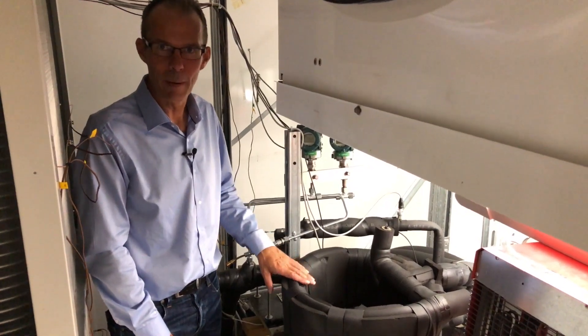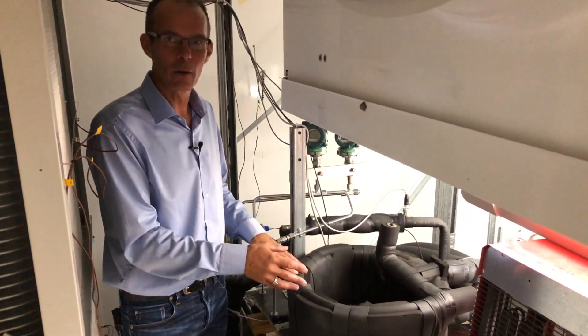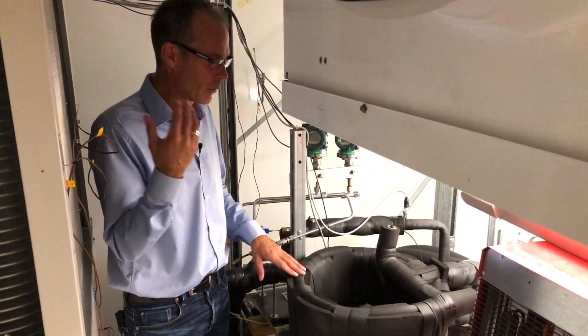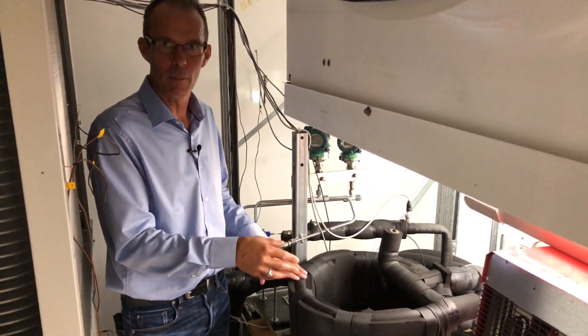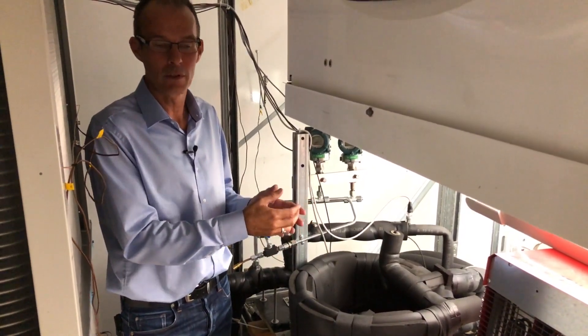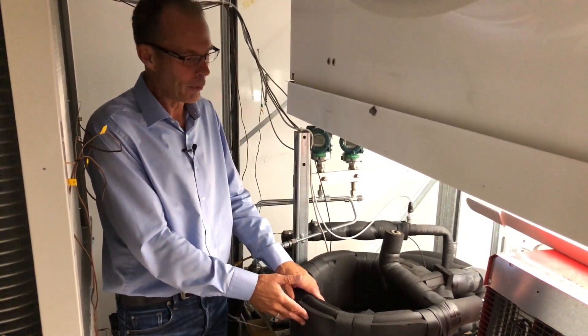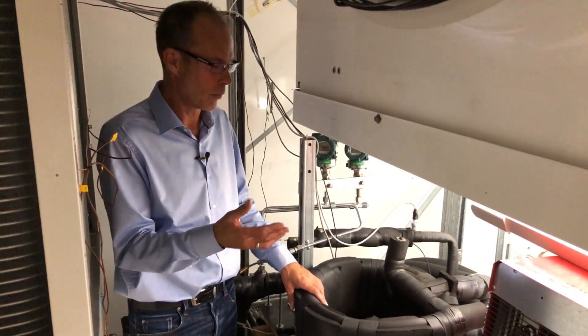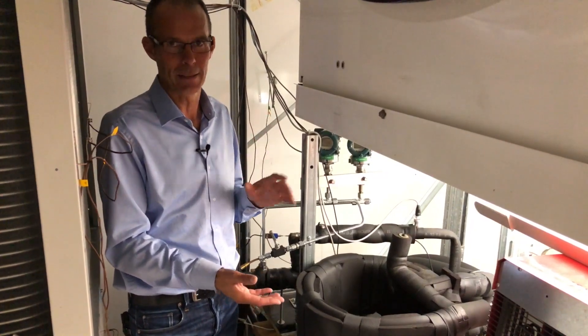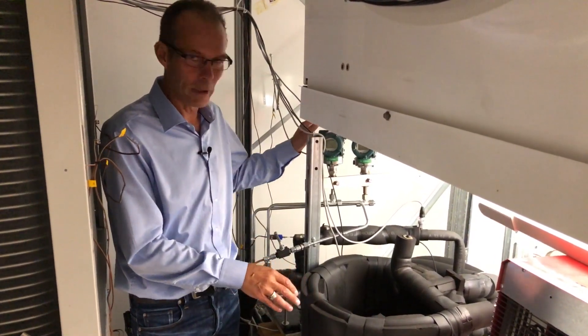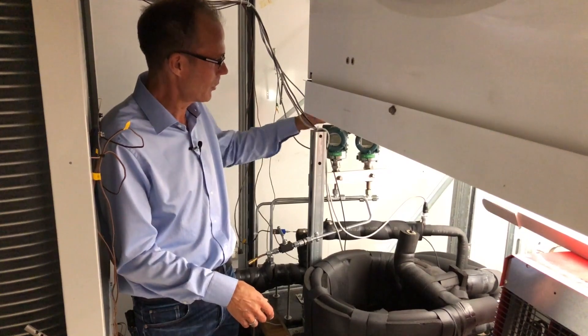This is the CO2 evaporator that is connected with the condensing unit. This CO2 evaporator is heated up by glycol that is conditioned outside the room and the control of the refrigerant is done by an expansion device which is controlling the CO2 refrigerant through the coil. The coaxial type of evaporator provides us a good superheat control and a good oil return for all variations of capacities. Inlet conditions of CO2 are measured with pressure and temperature and likewise outlet conditions are measured with pressure and temperature.